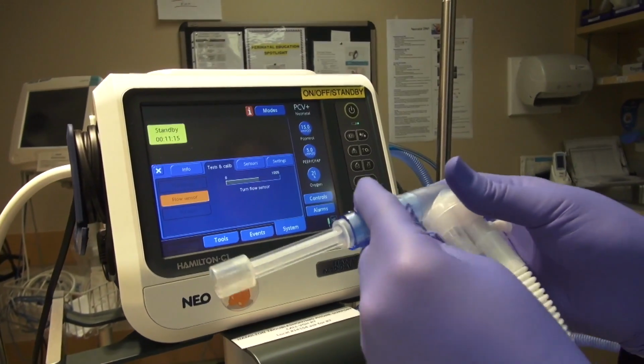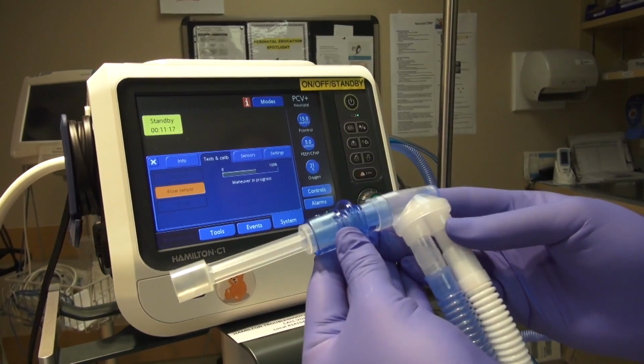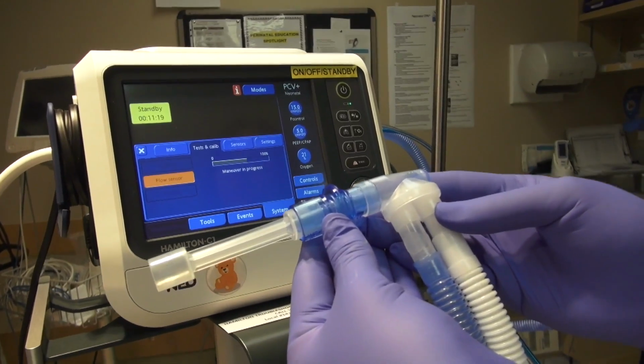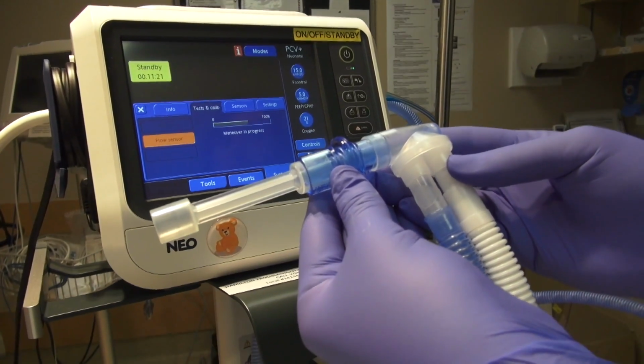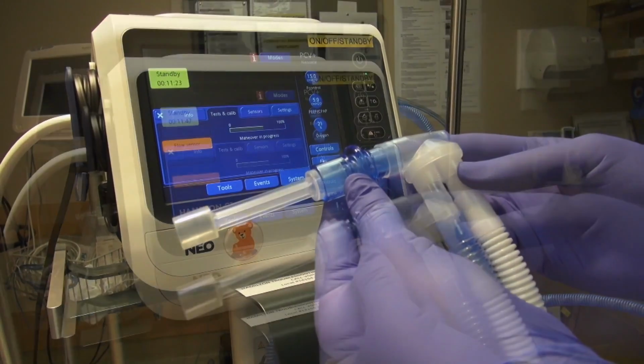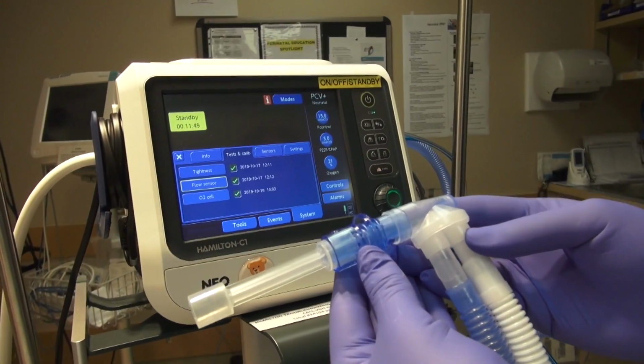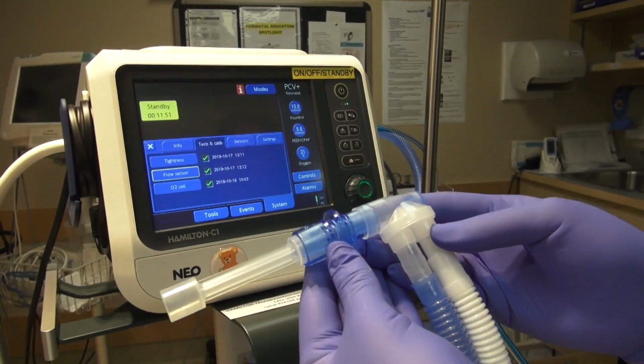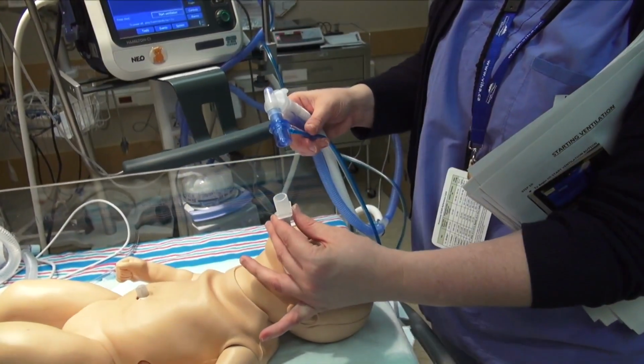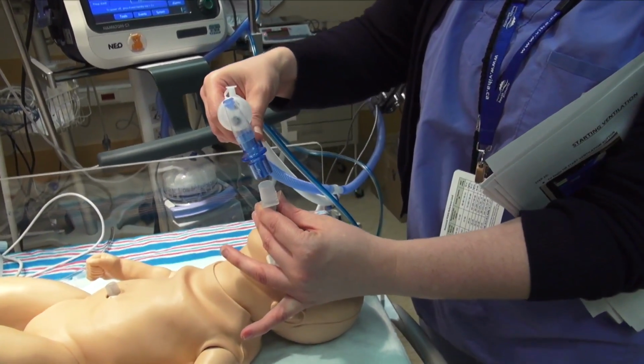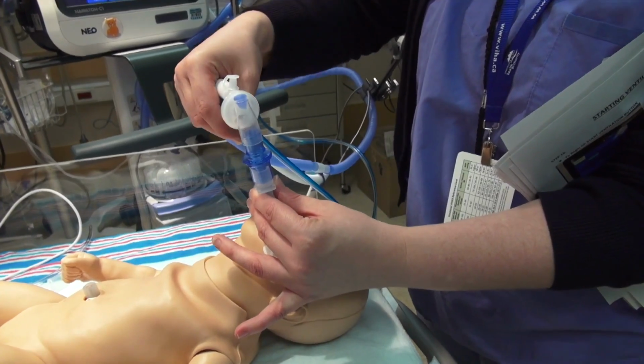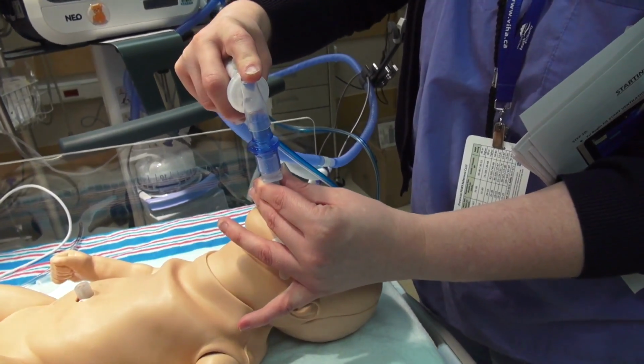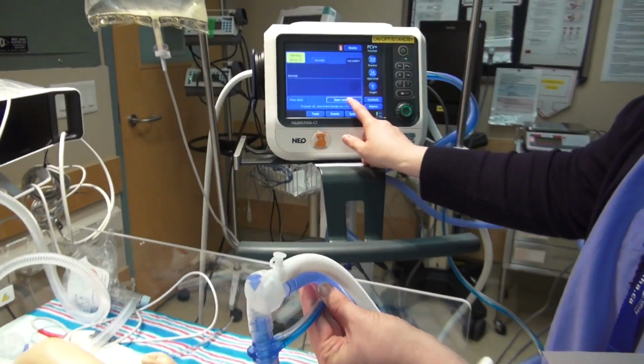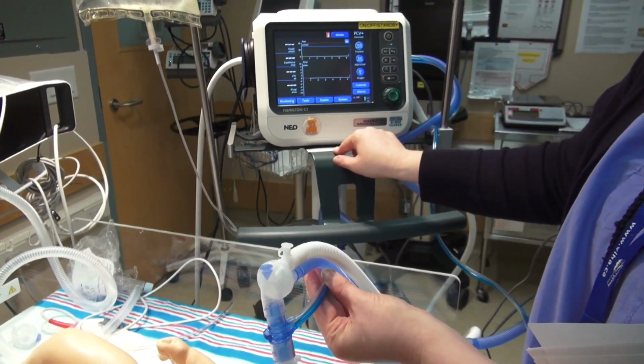Note, the O2 cell test is not mandatory and can be done on a PRN basis, and the vent will prompt you when to perform it. To begin ventilation therapy, attach flow sensor end to baby's ET tube and hit start ventilation.